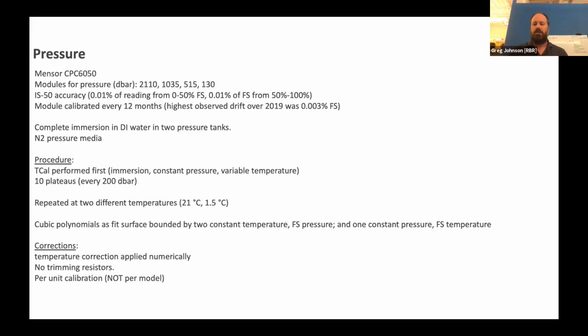In general, you wouldn't calibrate an oceanographic instrument in a gas, not least because gas is extremely compressible, and so to get up to those kinds of pressures, you're basically building a bomb. So what we do is we fill the tanks with water, and we pressurize only the lines that feed into them. That means that we have a very small volume that we're compressing, and so the amount of stored energy is low.